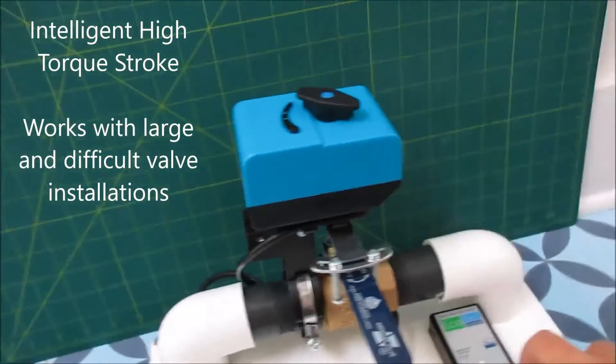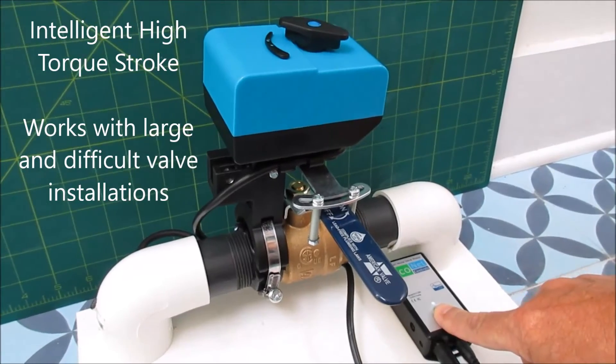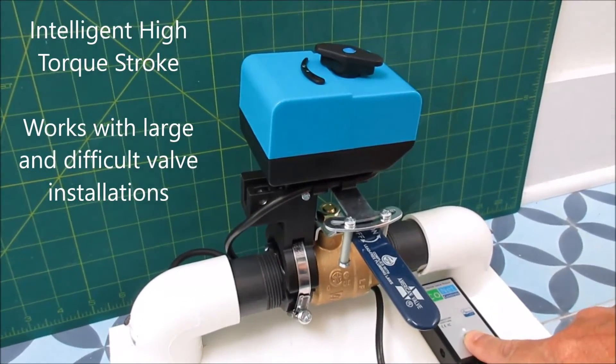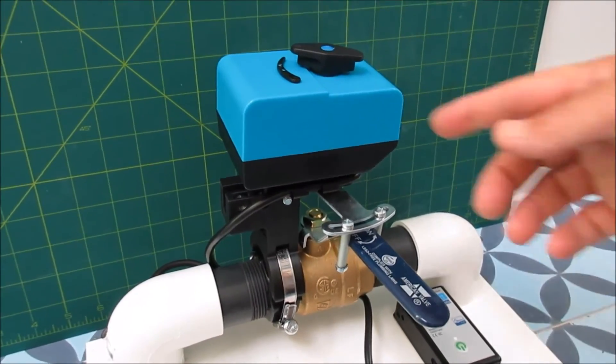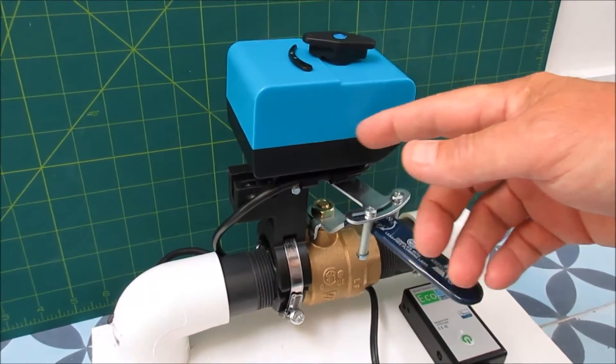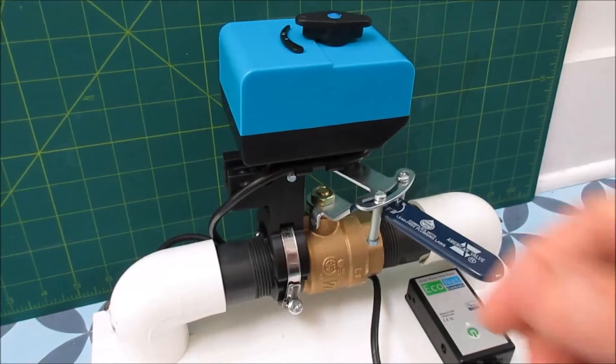I'm just going to show you the stroke for the open on this valve which happens to be difficult. Let's watch it. You can see it stresses out a bit. It moved maybe a few mils this way when it was getting the stroke started but then it recovered.